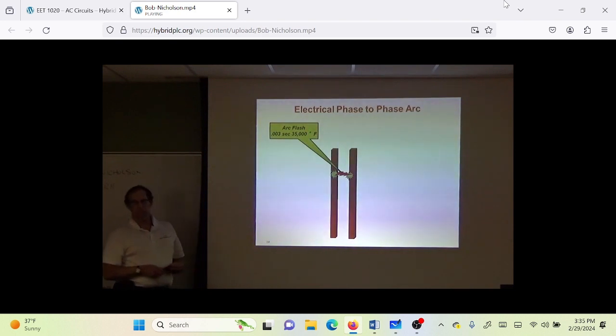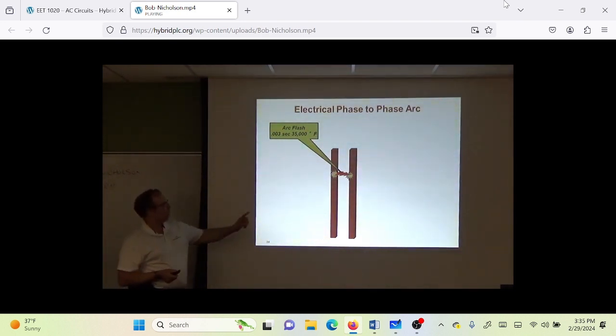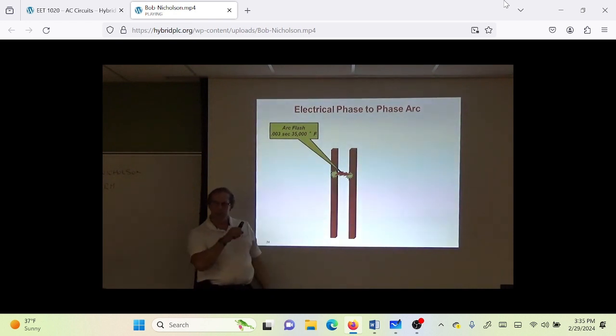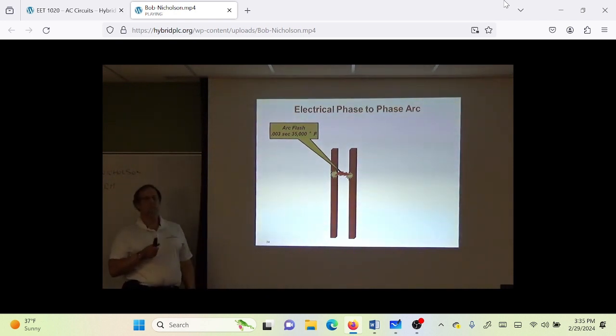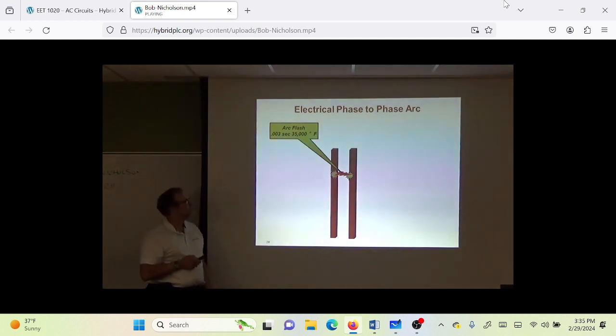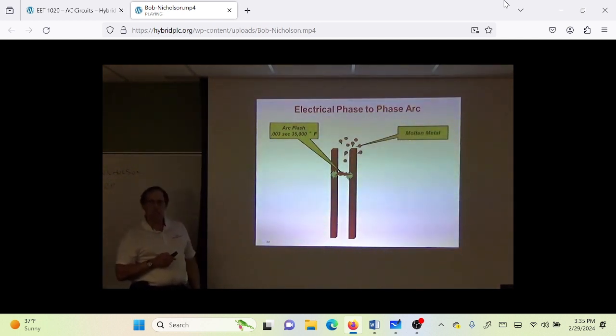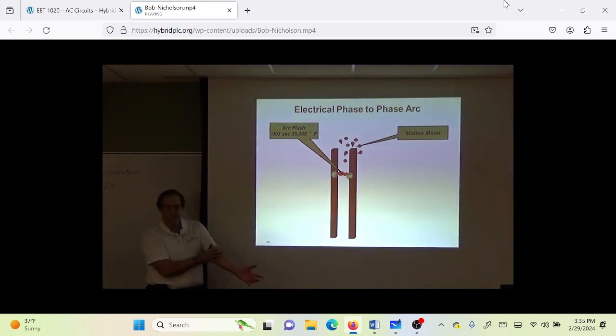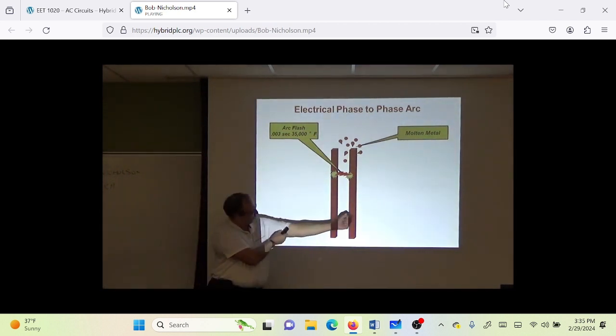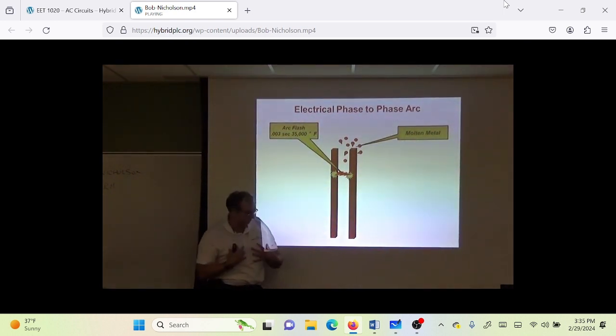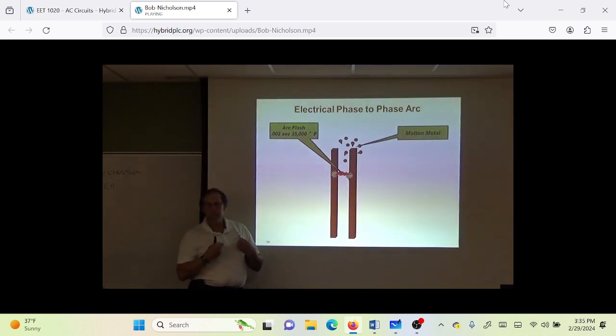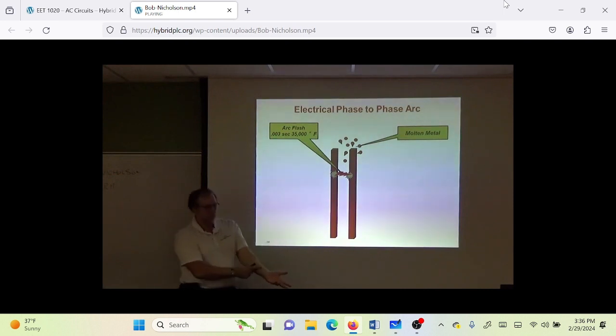It's 35,000 degrees. It's 4 times hotter than the surface of the sun because it's arcing through the air. The only thing hotter than this is a nuclear reaction on the Earth. The molten metal is what catches the clothing on fire. The arc flash crystallized my skin, which was bad. I had a short sleeve shirt on, and right there is where the short sleeve shirt stopped. Luckily, I did not have a heavy shirt on. I was far enough away. It crystallized the shirt and it fell off. If it would have been a heavy shirt, it would have ignited. It would have caught fire. There would have been enough fuel for it to catch fire. It did not. That molten metal bounced off here and burnt my skin.